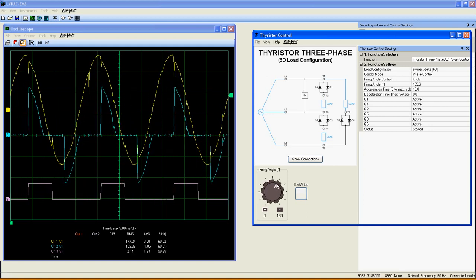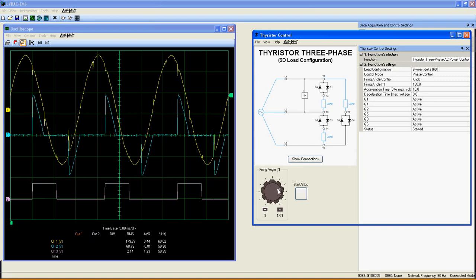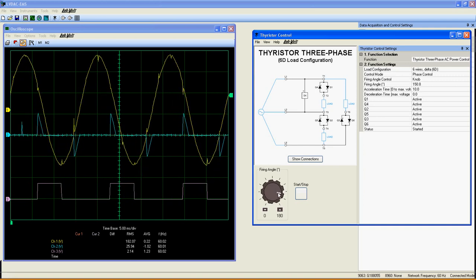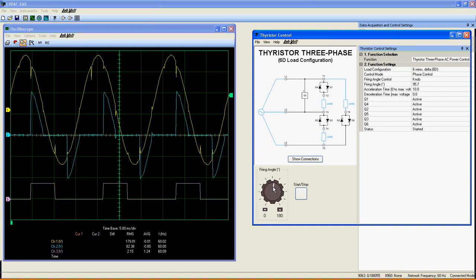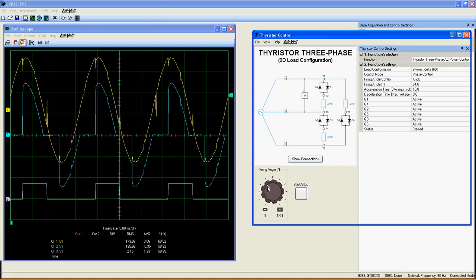Depending on the power factor or the line voltage of the network, you can adjust the firing angle, which causes the load, a reactance, to have a different value. In fact, you can easily absorb more or less reactive power from the network without using a synchronous compensator.